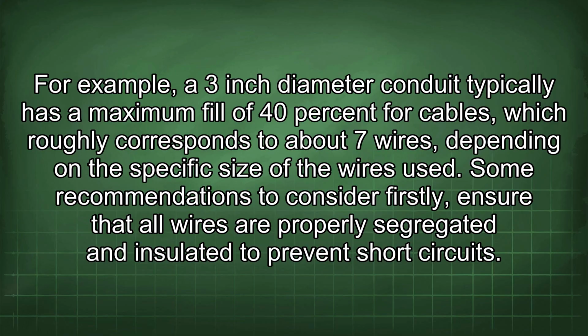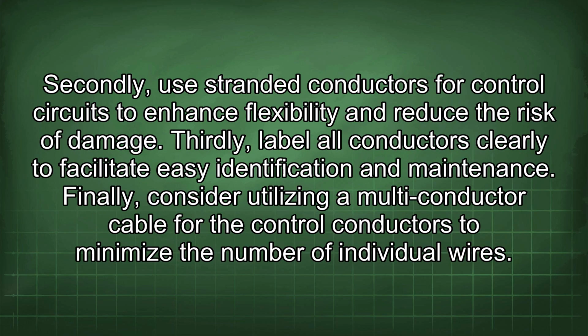Some recommendations to consider: firstly, ensure that all wires are properly segregated and insulated to prevent short circuits. Secondly, use stranded conductors for control circuits to enhance flexibility and reduce the risk of damage. Thirdly, label all conductors clearly to facilitate easy identification and maintenance. Finally, consider utilizing a multi-conductor cable for the control conductors to minimize the number of individual wires.